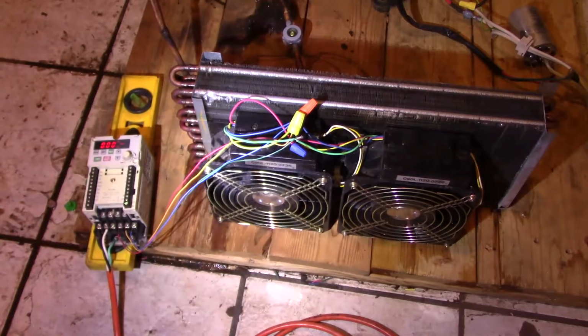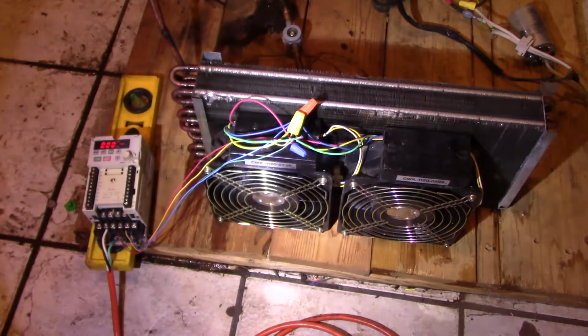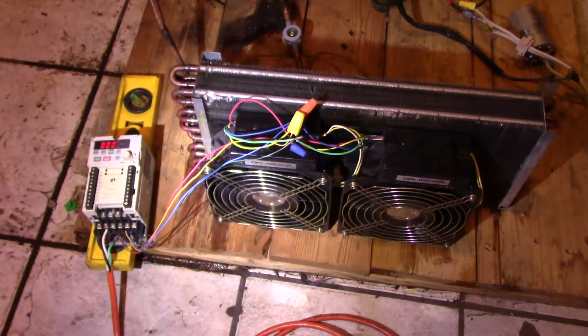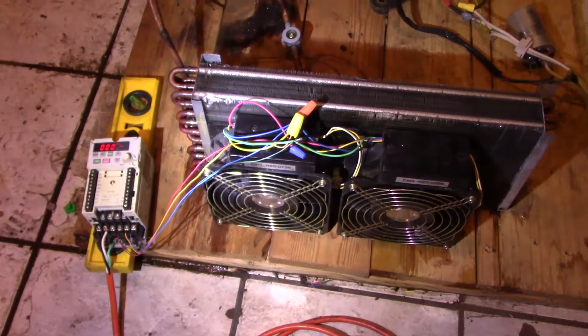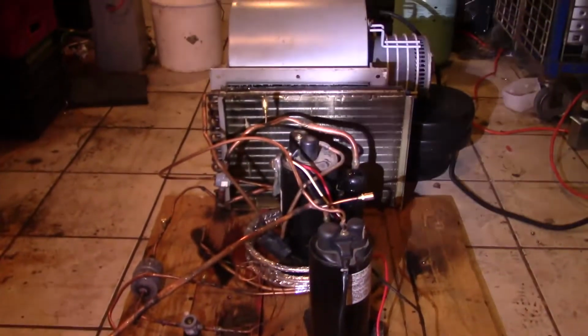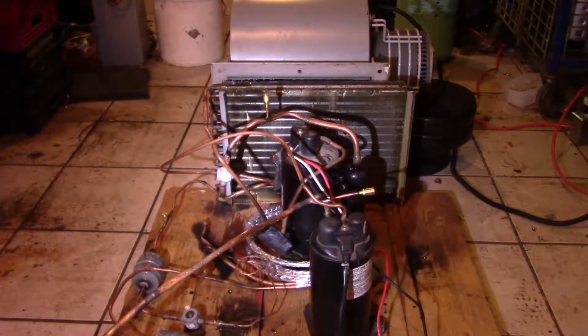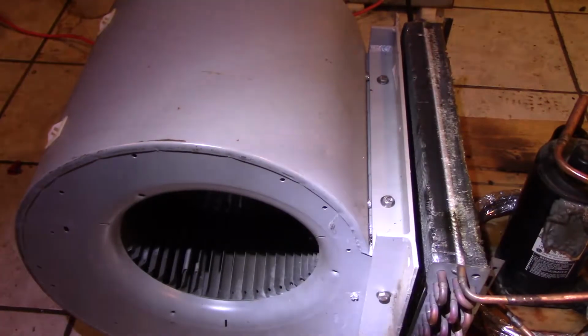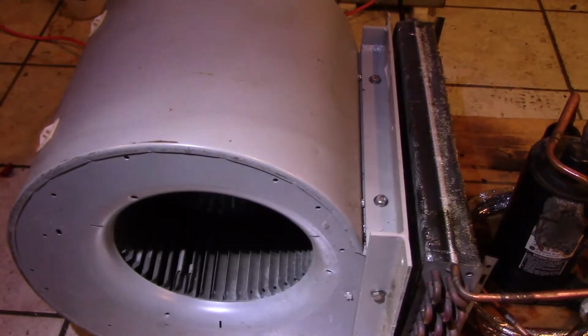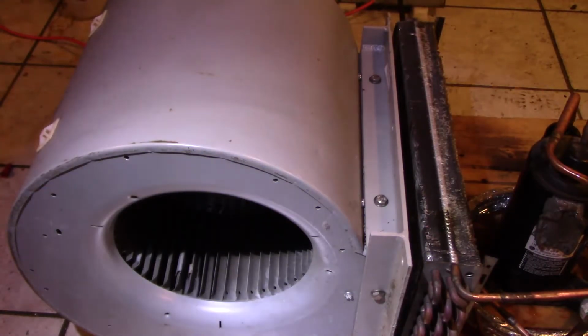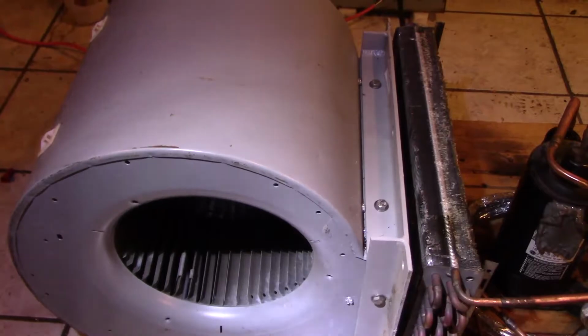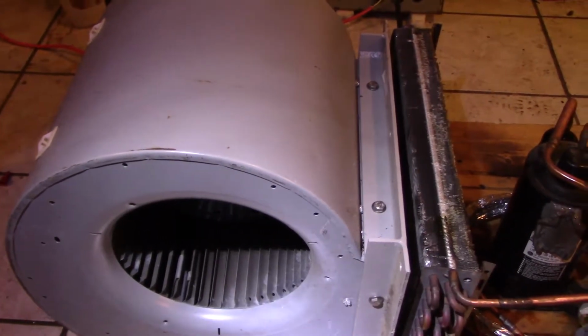Here's a view of the temporary prototype fans here for the evaporator, and they are 3-phase. There's a variable frequency drive there. I can control the speed of the fans, and likewise with the condenser there for the high temperature cycle. So obviously that's quite a fan for the condenser for the high temperature cycle. Now, as I said before, all the heat from the entire system has to come out through that condenser, so that's the reason for the oversized fan.